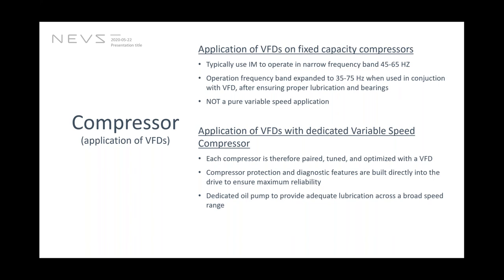If you look into the HVAC industry, the old compressors usually operated with a three-phase induction motor, which has a very narrow band of operation. So basically 50 Hertz for Asian and European countries, and 60 Hertz for North America. So 45 to 65 Hertz covered the whole range. But this was a very narrow band.